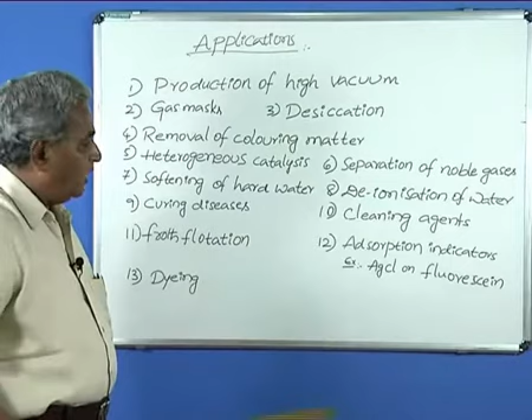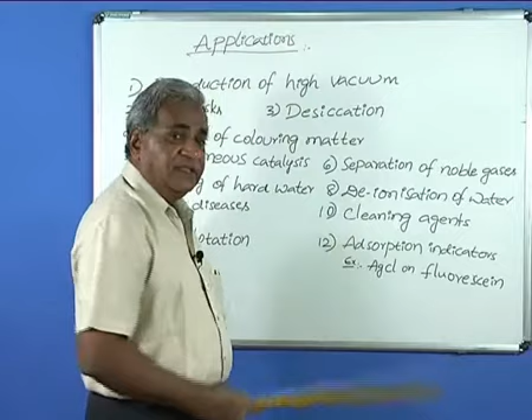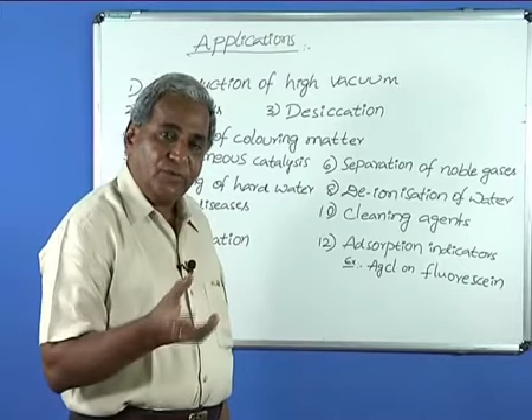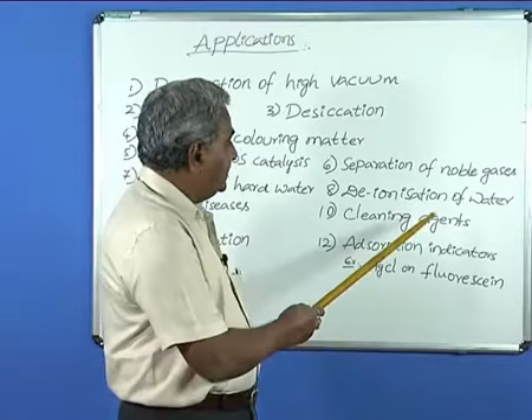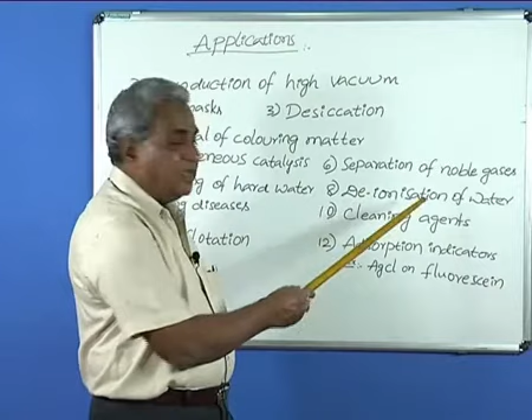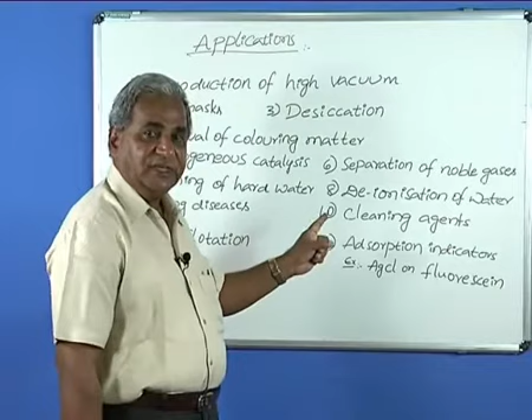Then deionization of water. If you see the ion exchange method for the removal of hardness of water, cations that cause hardness, that is calcium and magnesium, are exchanged by the cation exchange resins with hydrogen ions, and anion exchange resins allow sulfates and chlorides to be adsorbed on them and release OH minus to the water. H plus and OH minus obtained from the cation exchange resin and anion exchange resin form water. In that way, both cations and anions that cause hardness are removed, and H plus and OH minus ions are sent into water. That is why the process is called deionization, removal of ions. In the ion exchange method, you come across this phenomenon.